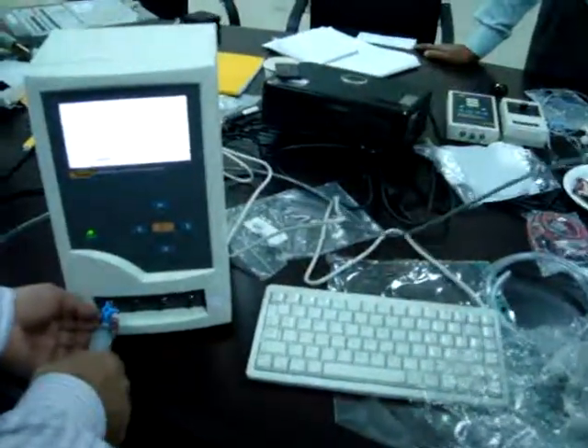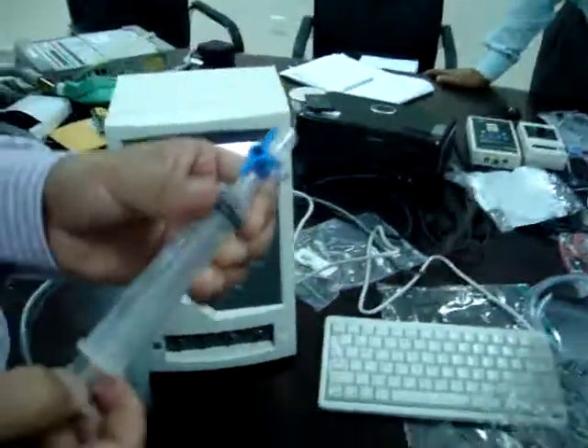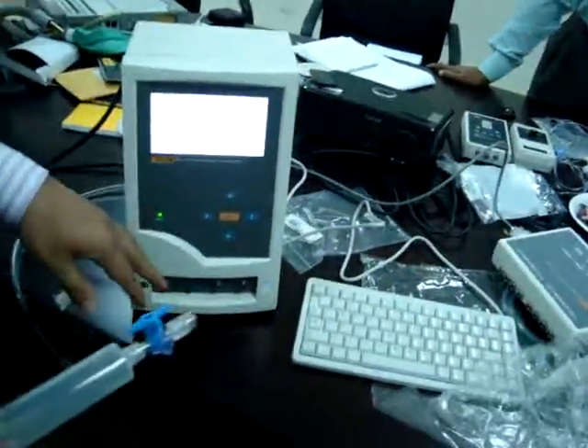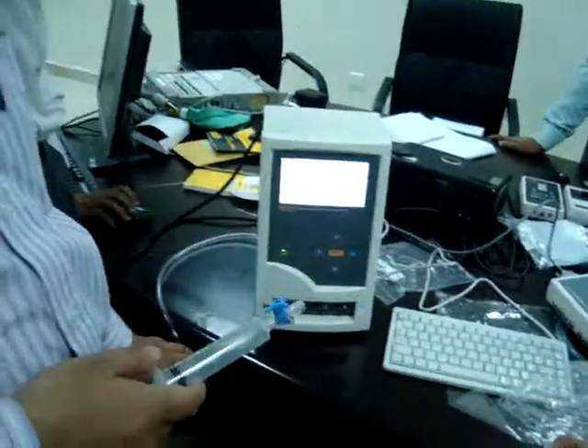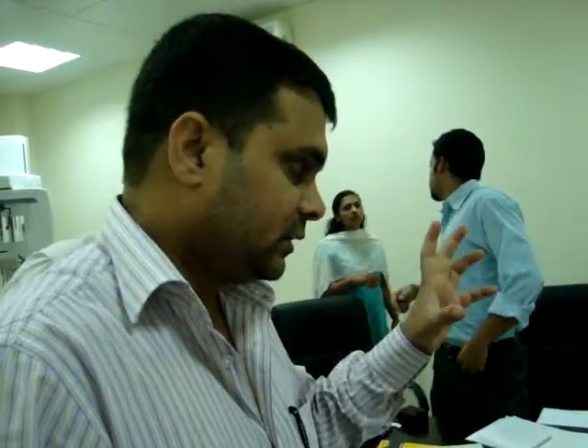Okay. So what we need to do, we need a syringe to prime it first, before measurement starts, the system should be filled with liquid. Okay. Now, one precaution you have to take here: don't use tap water for this purpose. Don't use any medical solutions. Okay. Use only deionized water, or if you can get distilled water from your lab. Yes. Or just the water they use for diluting in injections and all.